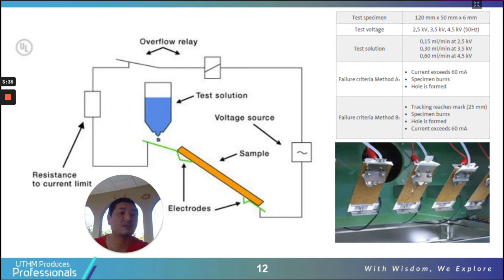The specimen, the dimension of the test sample. So the voltage supply is 2.5 kV, 3.5, 4.5, and so on. And then the test solution, the water, is supplied at 0.15 milliliter per minute. And then the failure criteria method. So if the current exceeds 60 milliamp, or the specimen burns, or a hole is formed on the surface, then the insulation failed. So this is the idea, to check whether the insulation has failed or passed the test.